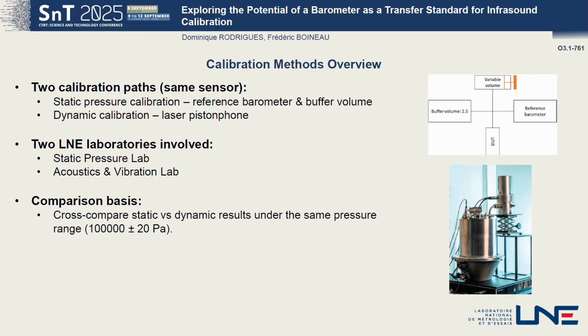Okay, so a few words about the calibration method. We used two calibration methods. The static calibration was performed by my colleagues from the LNE, the Static Pressure Lab in Paris. They used a method by comparison against a reference barometer and by using also a buffer volume to stabilize the steps of static pressures.